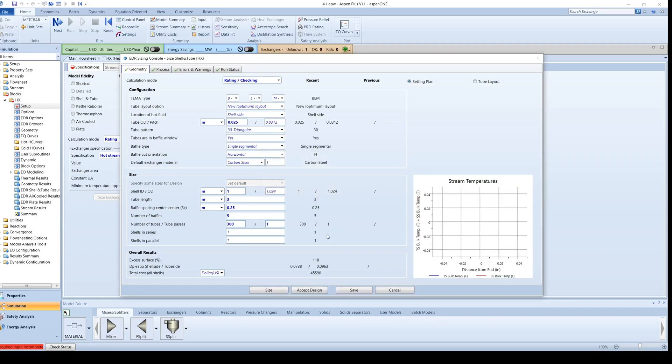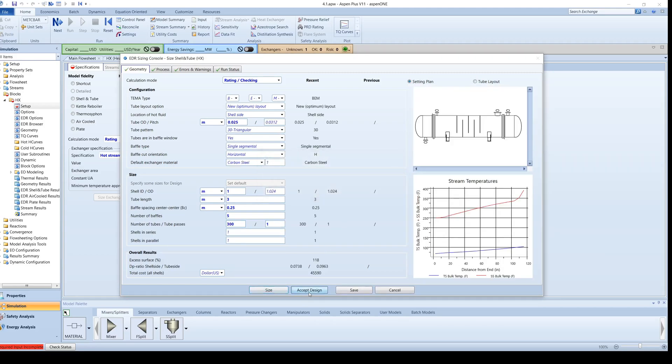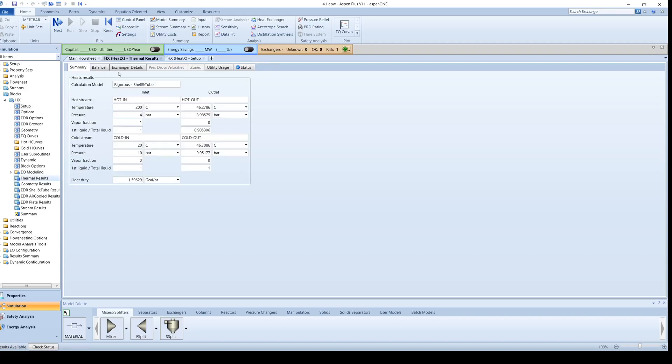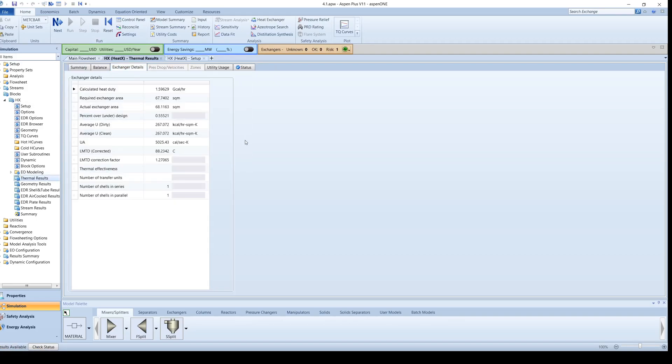Click on Size and then accept the design. Run the simulation and click on Thermal Results in the menu tree. Notice how the actual exchanger area is only slightly larger than the required exchanger area. This means that the heat exchanger is only slightly over-designed by about 0.45%.